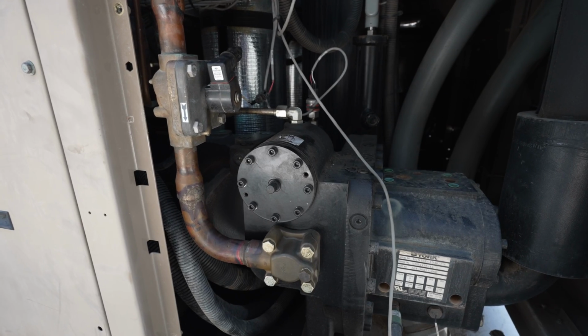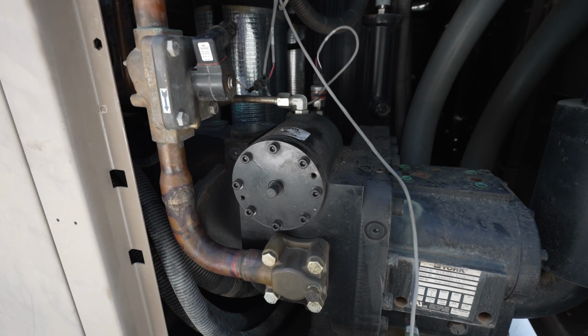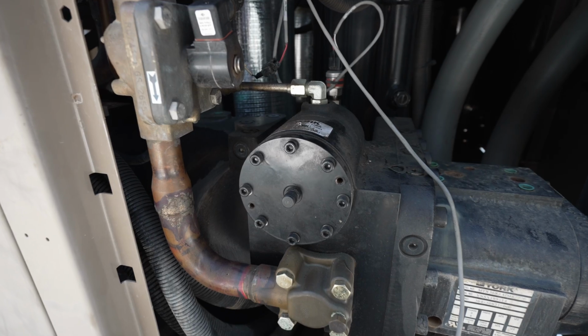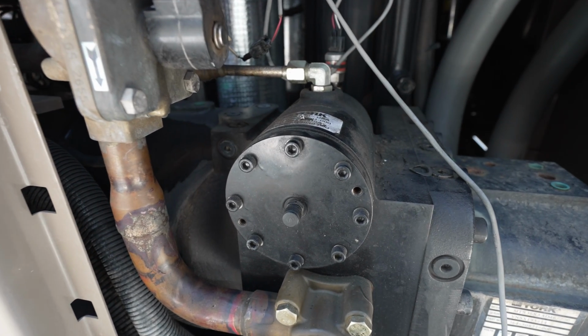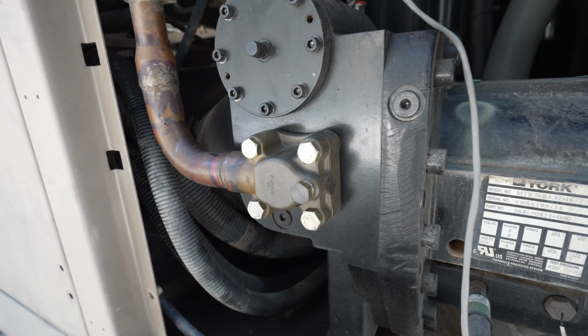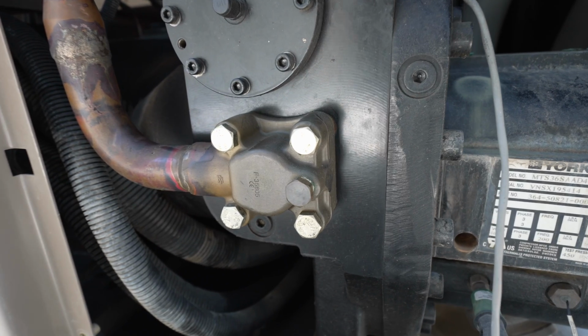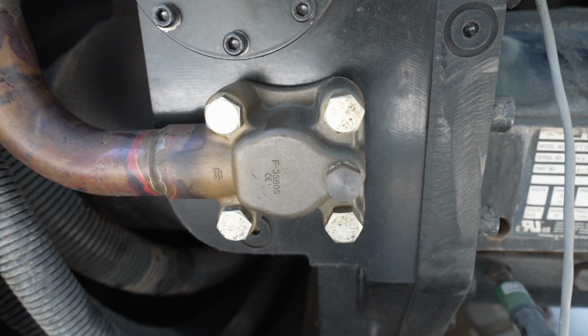That's one of the drawbacks to, say, the brazed plate style, is you still have a heavy subcooling, but you're getting flash gases to the evaporator. Now, York uses this commonly on a lot of their air-cooled machines. YCIV, YVAA both have flash tank economizers. And at the top of the tank, there is a suction line or an economizer line that comes back and feeds into the side of the compressor, but it's still part of the suction pressure of it. It's not coming into the actual suction line.